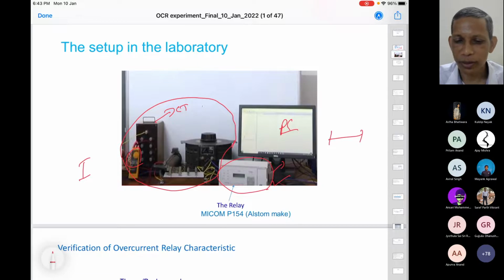Even during normal situations, it can be hundreds or thousands of amperes, depending on the capacity of the particular feeder line or device. Because this is a numerical device with a 5 amp, 1 amp input, we cannot have thousands of amperes input to such a device. It cannot manage that. If we did, the size and cost of the device would be too high. And this part is nothing but a detector part. So why should we have a detector of similar size to a transformer? Agree? That is not welcome investment-wise also.